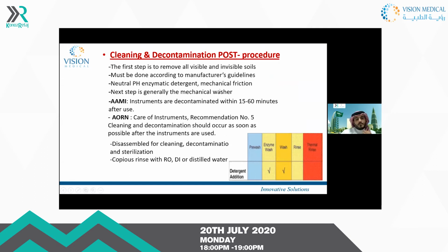And cleaning with decontamination after the procedure: the first step is to remove all visible and non-visible soils. This must be done, as we mentioned, according to the manufacturer guidelines. We have to check neutral pH, enzymatic detergent, and mechanical friction. The end stage will be thermal disinfection or the mechanical washer. We have some standards, and I brought the most used in our guidelines here in Saudi Arabia. The AAMI: instruments are decontaminated within 15 to 60 minutes after use.